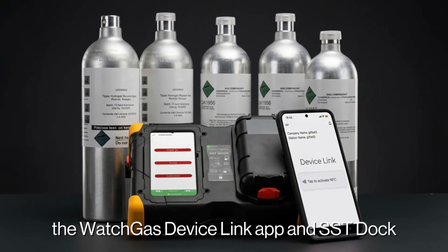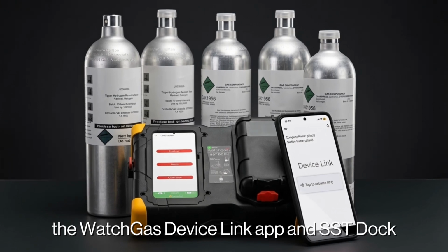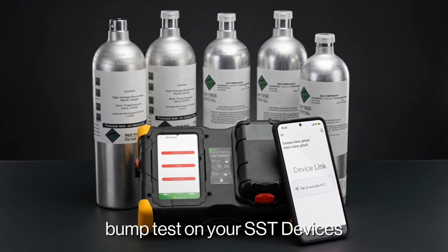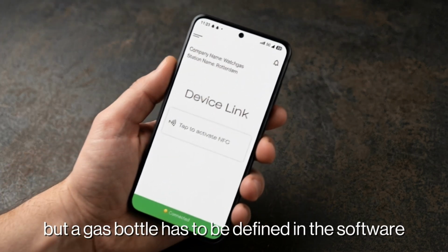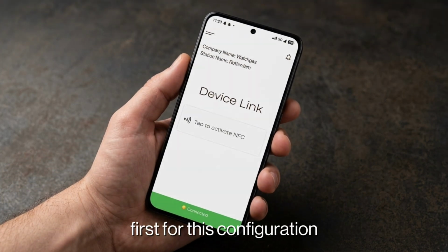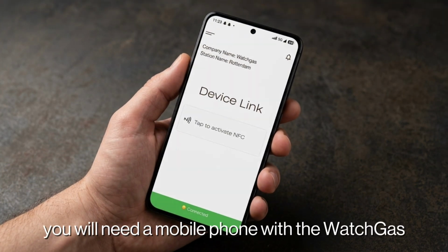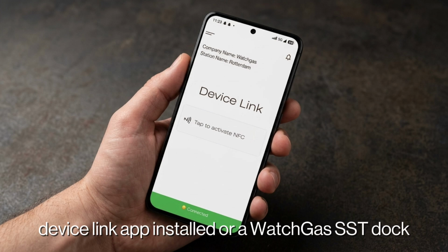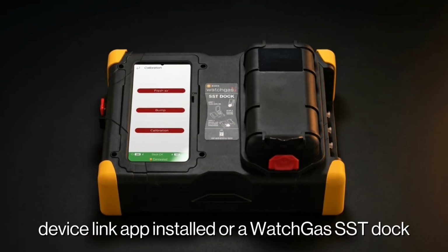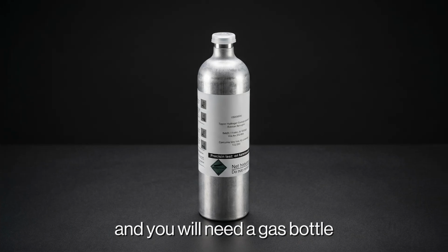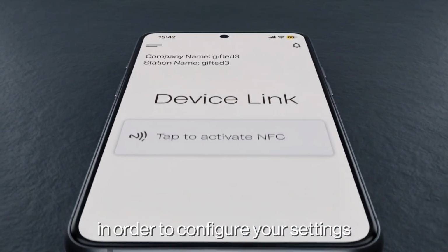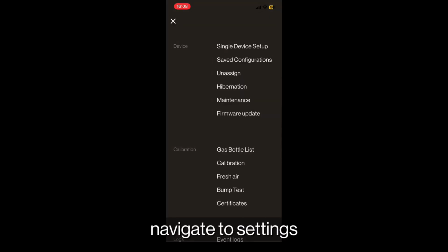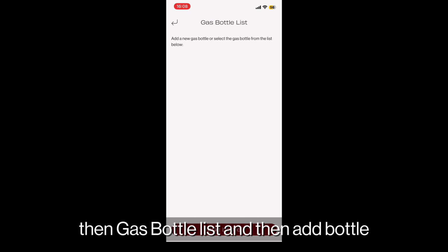The WatchGas device link app and SST Dock can perform calibration and bump test on your SST devices, but a gas bottle has to be defined in the software first. For this configuration, you will need a mobile phone with the WatchGas device link app installed or a WatchGas SST Dock, and you will need a gas bottle. In order to configure your settings, navigate to Settings, then Gas Bottle List, and then Add Bottle.